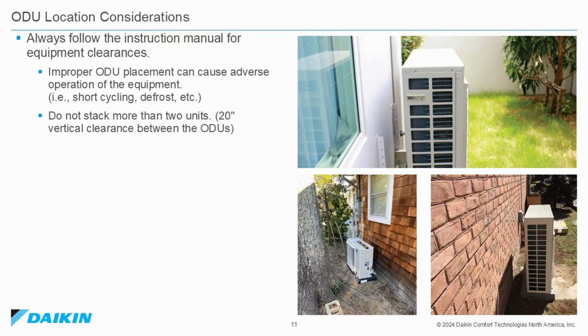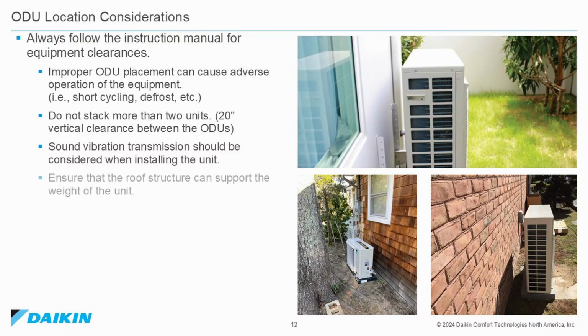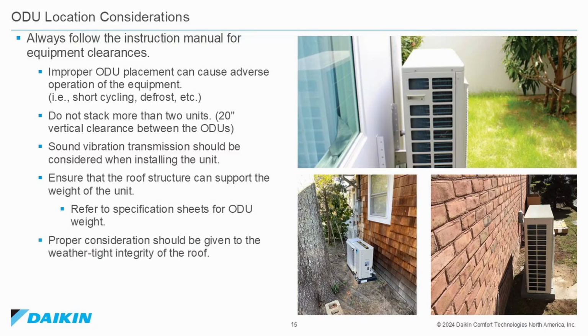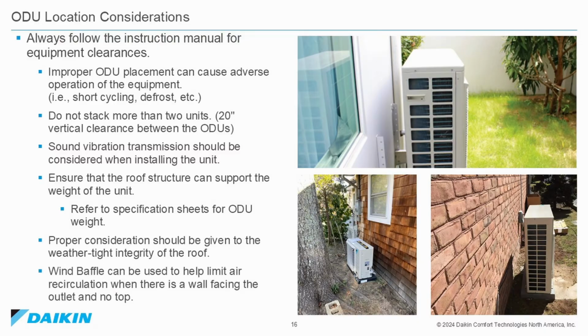Do not stack more than 2 units and leave at least 20 inches vertical clearance between the outdoor units. Sound vibration transmission should be considered when installing the outdoor unit. Ensure that the roof structure can support the weight of the unit. Refer to the specification sheet for outdoor unit weight. Proper consideration should be given to the weather-tight integrity of the roof. Wind baffles can be used to help limit air recirculation when there is a wall facing the outlet and no top.